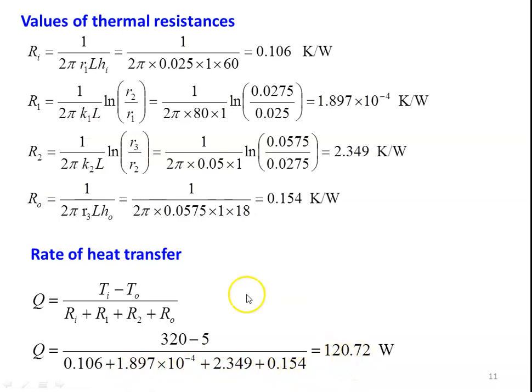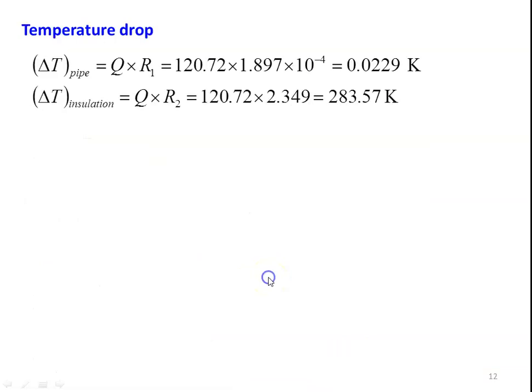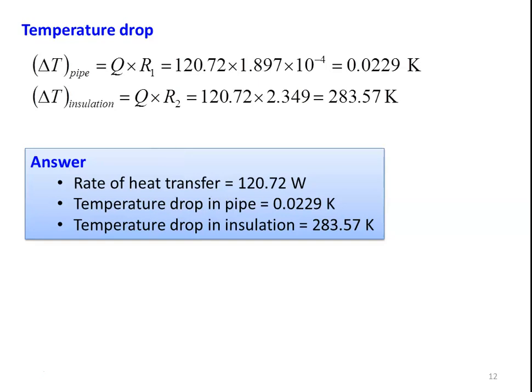The rate of heat transfer Q = (Ti - To)/(Ri + R1 + R2 + Ro) = (320 - 5)/(0.106 + 1.897×10⁻⁴ + 2.349 + 0.154) = 120.72 W. Temperature drop across the pipe: Q·R1 = 120.72 × 1.897×10⁻⁴ = 0.0229 K. Temperature drop across the insulation: Q·R2 = 120.72 × 2.349 = 283.57 K.